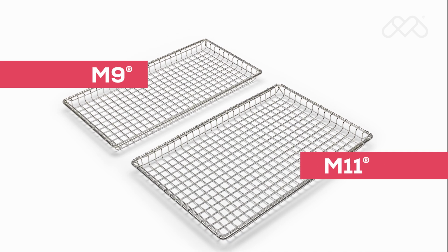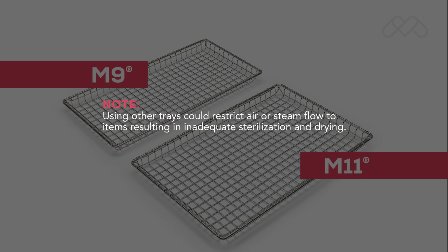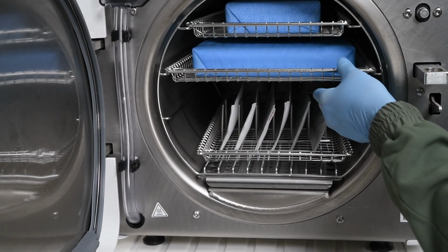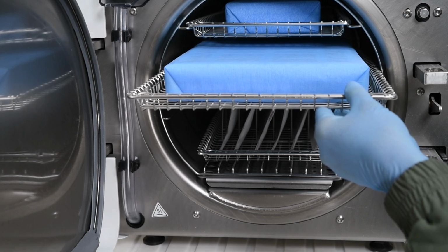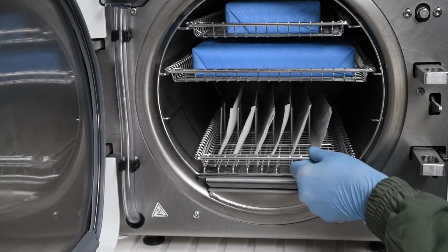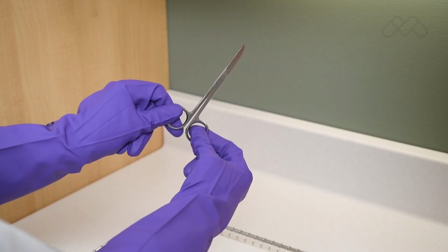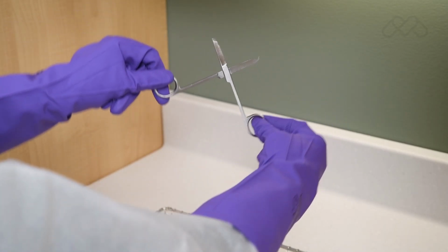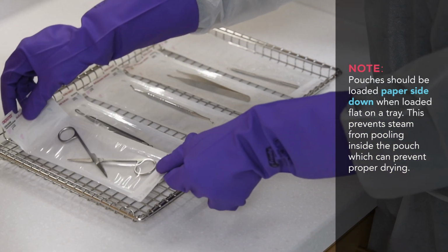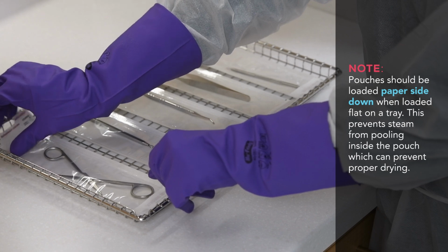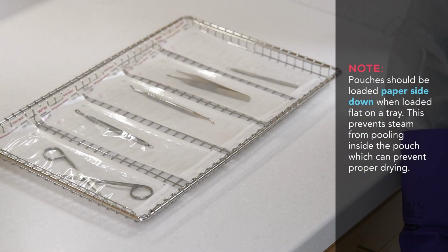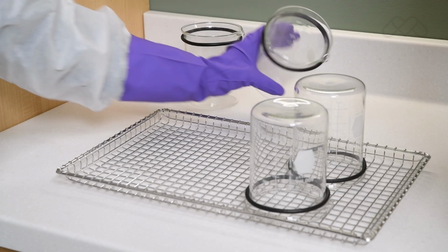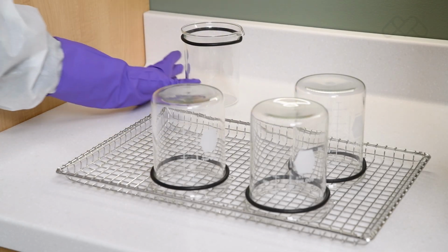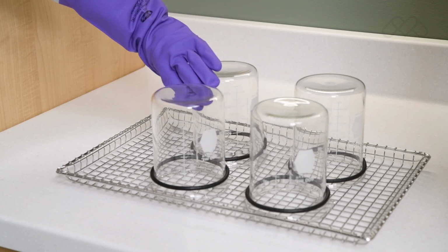Use only M9 and M11 trays and use them only in the corresponding sterilizer. Using other trays could restrict air or steam flow to items, resulting in inadequate sterilization and drying. All items must fit within the sterilizer tray and not extend over the lip of the tray. Instruments must not scrape the chamber walls when sliding the tray into the chamber. Jointed items must be sterilized in an open position so all surfaces are exposed to the steam. Reusable instruments, devices, and items must be arranged in a single layer on the trays to permit proper steam flow and drying. Glassware or utensils capable of holding water should be positioned on the tray with the open side down so any water condensate drains from the container.